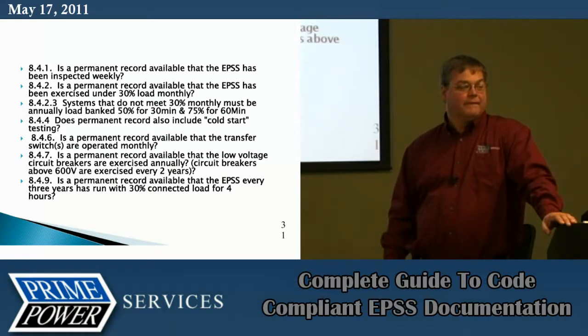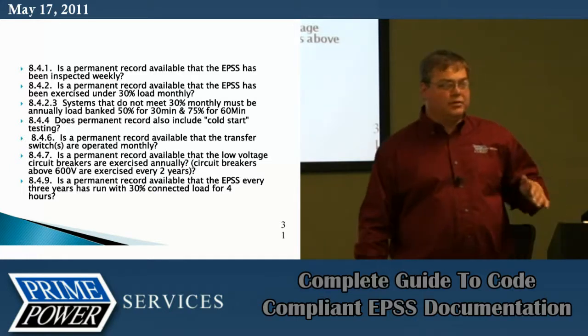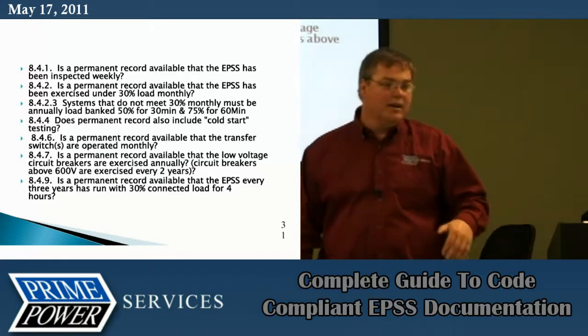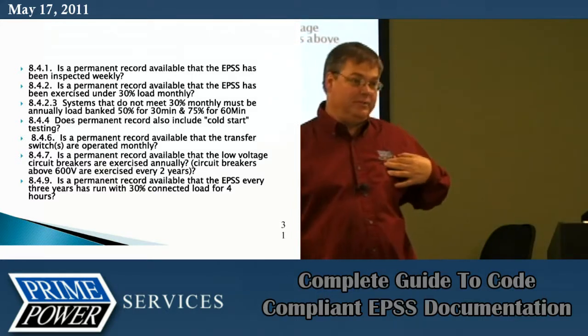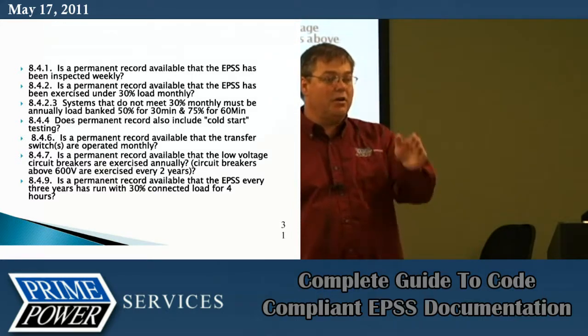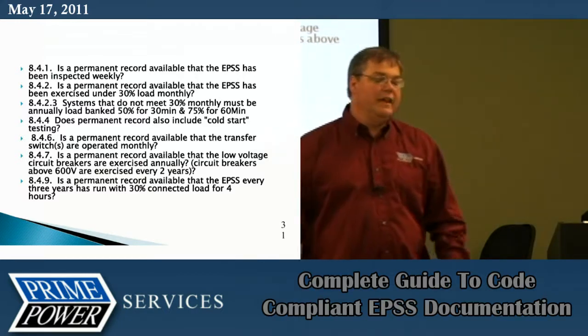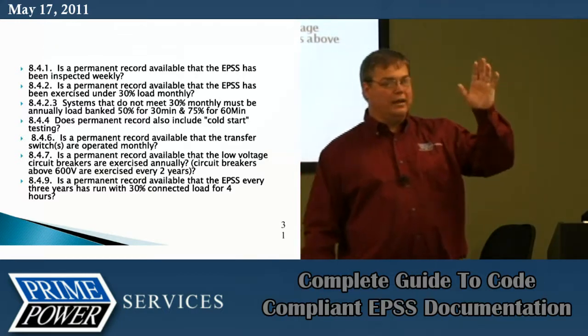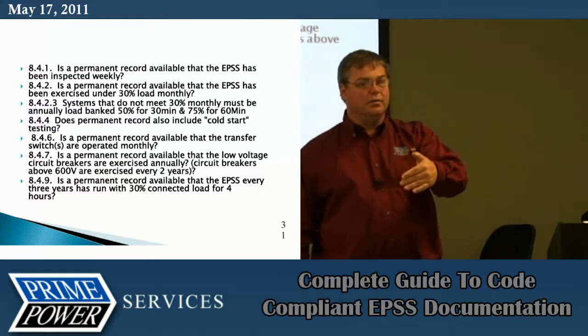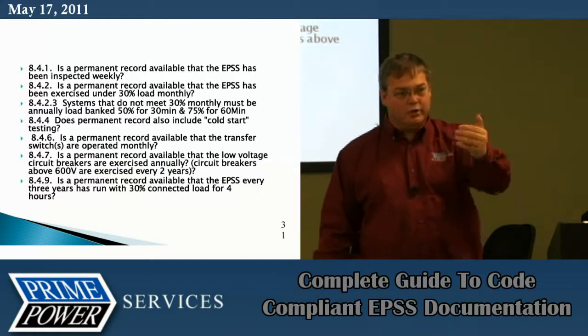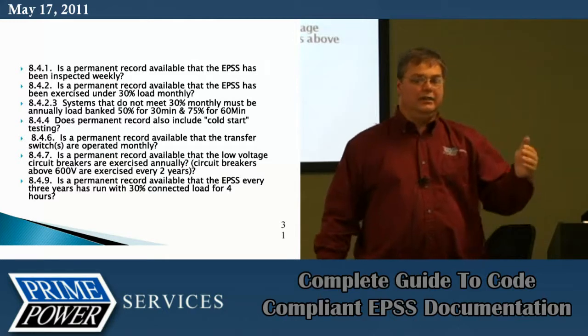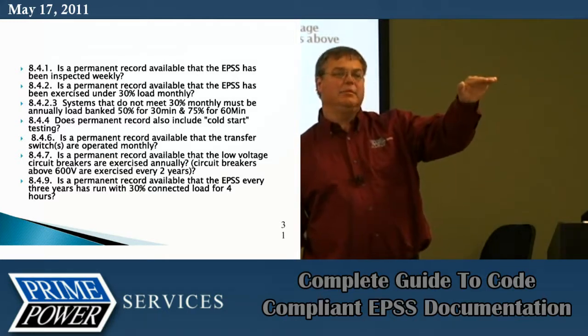Does it talk about doing injection testing? No, not in here. But is that going to be a Joint Commission requirement? I doubt it because hospitals, I can't speak for George Mills and all the cohorts up there, but I doubt you'll ever see that. Terry Parish's opinion: I doubt you'll ever see that in Joint Commission because of the patient safety issue. They don't want you to go in and cut stuff off when you got patients in the hospital. Whereas in NFPAs, after testing the equipment, they want you to test the equipment. And in Joint Commission, they put that life safety a little bit above that.